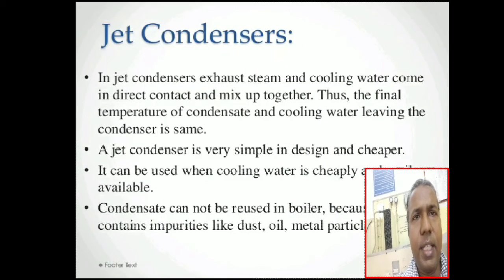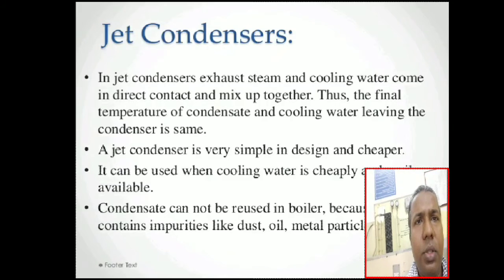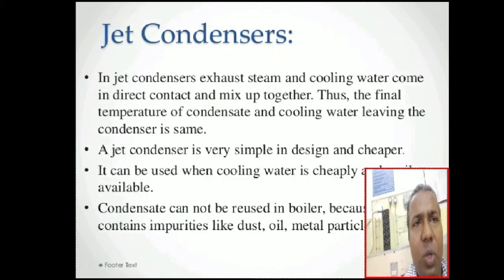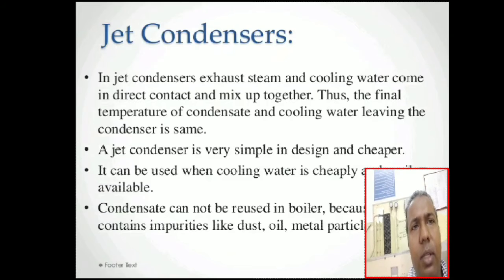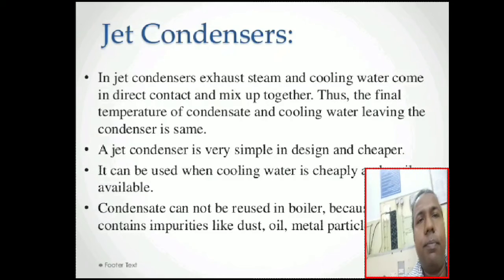Now let us see the jet condenser. In a jet condenser, exhaust steam and cooling water come in direct contact and mix together. Thus, the final temperature of the condensate and cooling water leaving the condenser is the same. In this, the steam coming from the turbine directly mixes with the makeup water provided in the condenser. Because of this mixing, the outcome of the condenser is at the same temperature as the makeup water we have provided into the condenser.